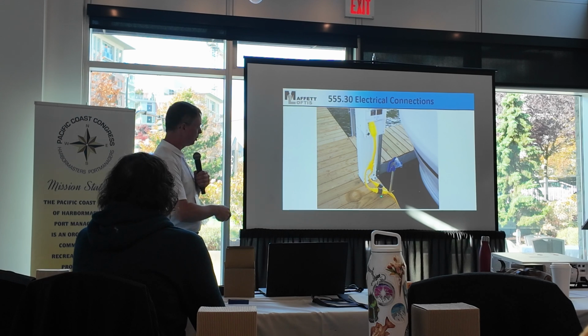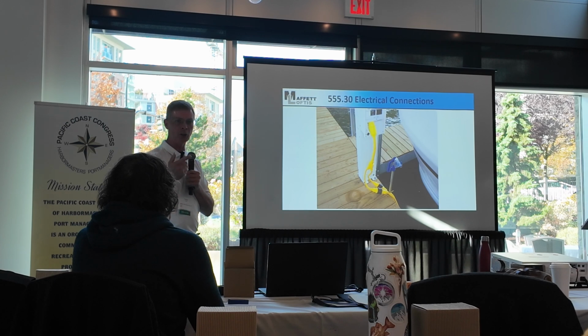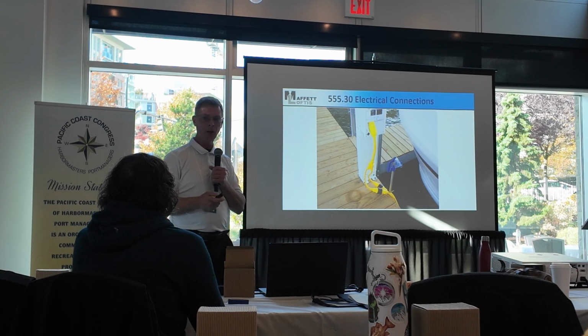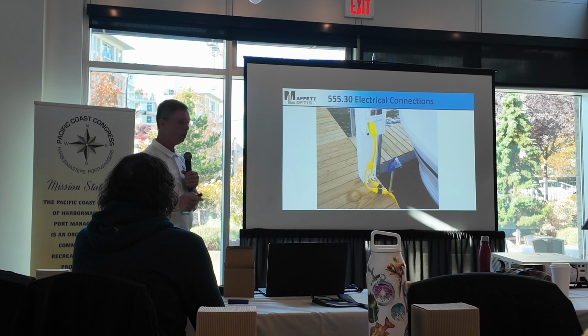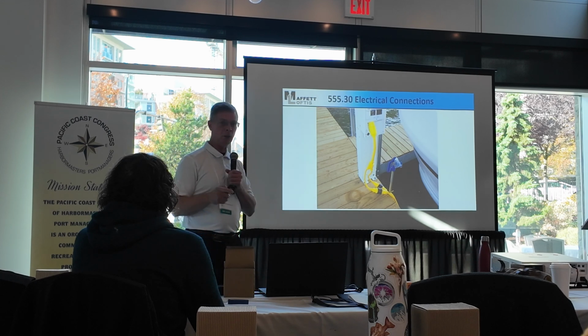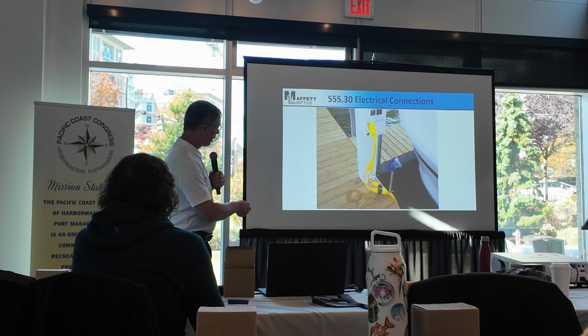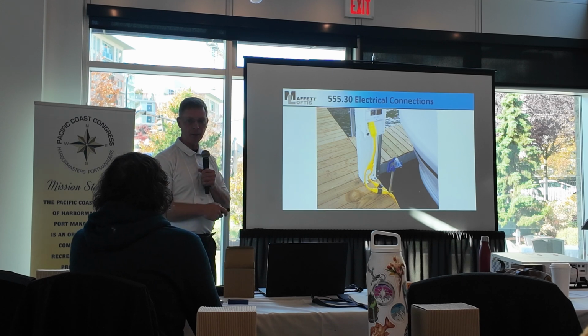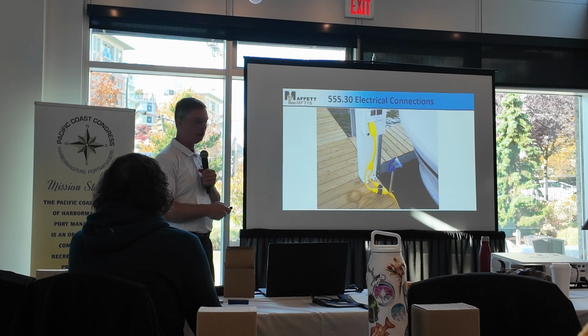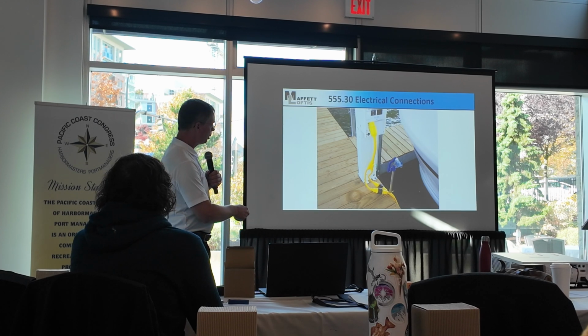Another thing is, this is below the electrical datum plane, and all electrical connections are supposed to be above the electrical datum plane. For a floating dock, it's 12 inches off the deck and 30 inches off the water. This is obviously below that. The biggest problem is this. What is that cord right there? You know what voltage it is? It's a 50 amp, 240 volt. That's a number 6 wire.